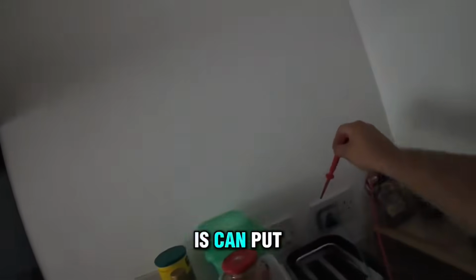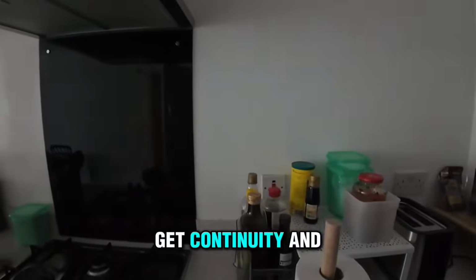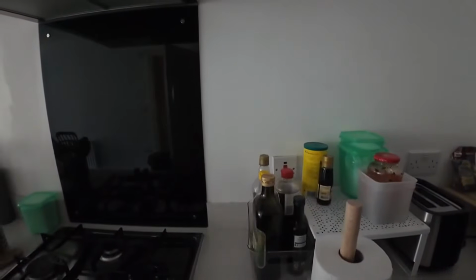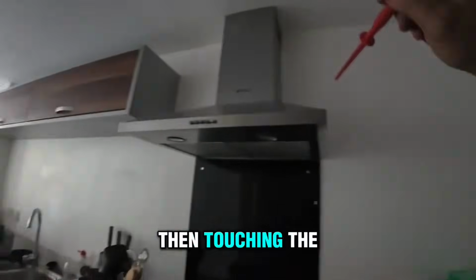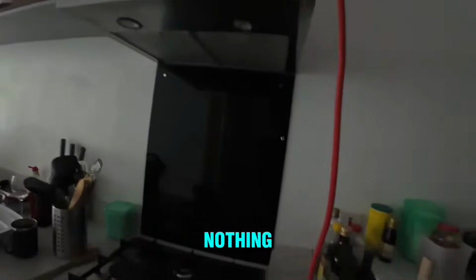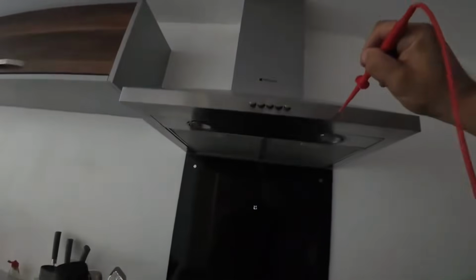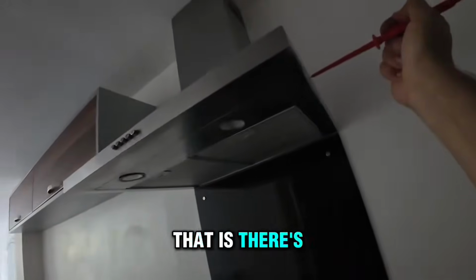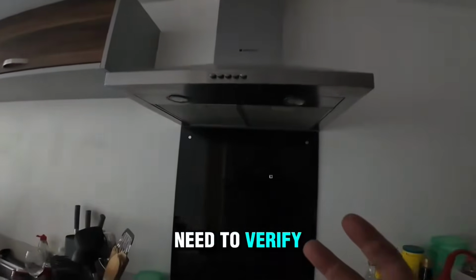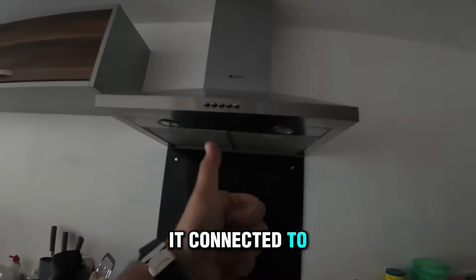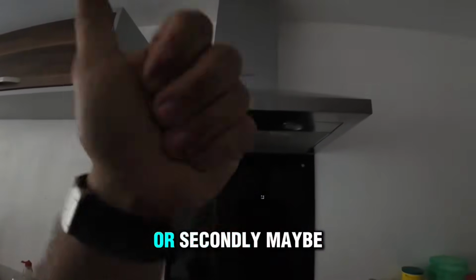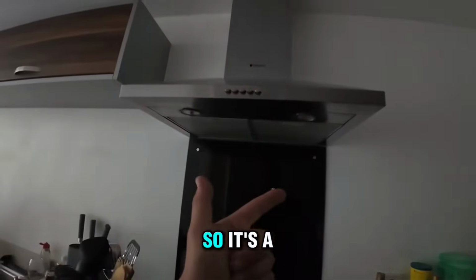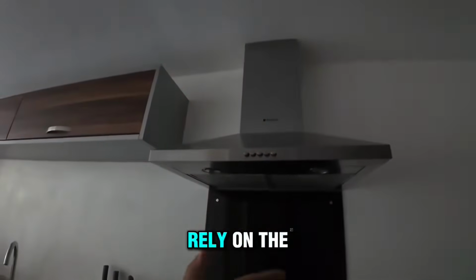So now I know that my one cable is put into the earth pin of the socket, and when I do that, I get continuity. And if we null the leads, so if I put it in the socket and then touch the metal enclosure, nothing. So it appears that there's no continuity. So there are two things we now need to verify. First one, is it connected to the earth properly as it should be? Or secondly, maybe it's double insulated, so it's a class 2 appliance and it doesn't rely on the earthing.